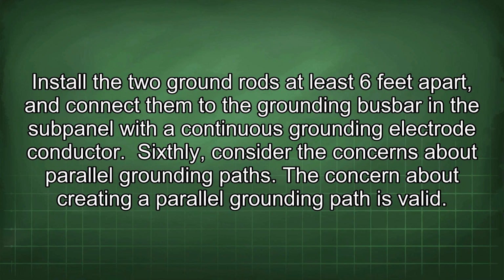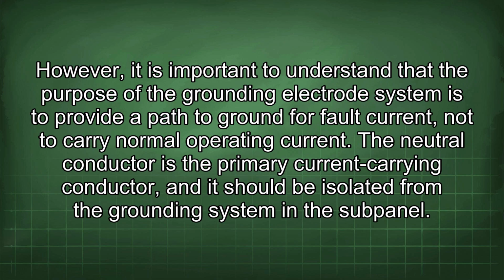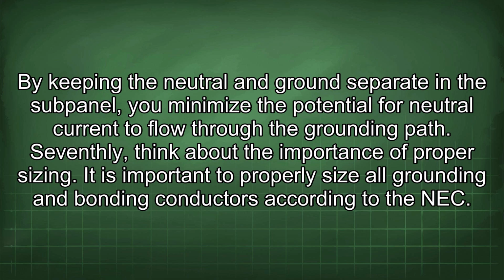Sixthly, consider the concerns about parallel grounding paths. The concern about creating a parallel grounding path is valid. However, it is important to understand that the purpose of the grounding electrode system is to provide a path to ground for fault current, not to carry normal operating current. The neutral conductor is the primary current carrying conductor, and it should be isolated from the grounding system in the subpanel. By keeping the neutral and ground separate in the subpanel, you minimize the potential for neutral current to flow through the grounding path. Seventhly, think about the importance of proper sizing. It is important to properly size all grounding and bonding conductors according to the NEC.